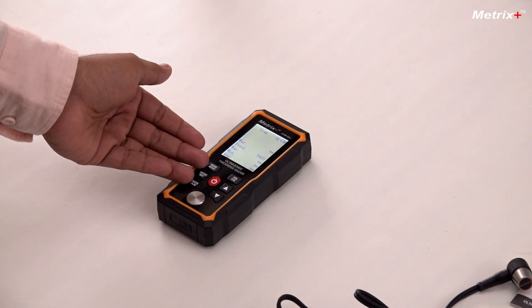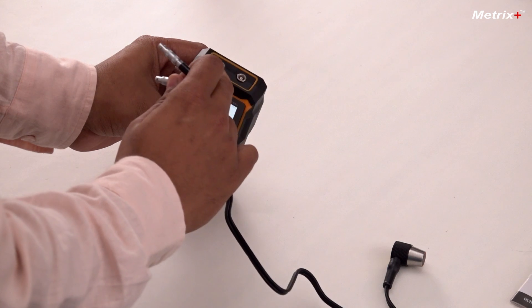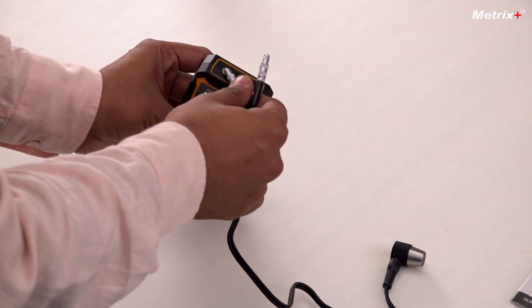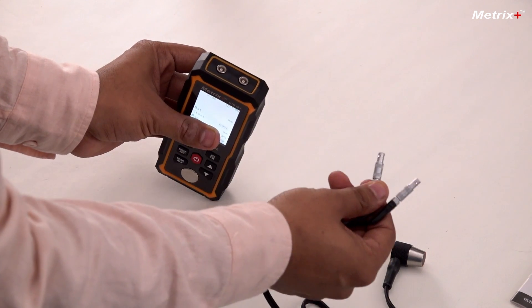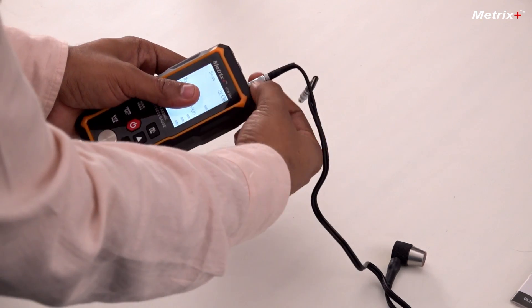First I'll just show how to measure using this meter. So first we connect the probes. There are two connections and you can connect anywhere — there is no limit on whether you connect this here or here. But it should be tight, so once I connect this, I have to tighten the screws. You should make sure that it is tight.